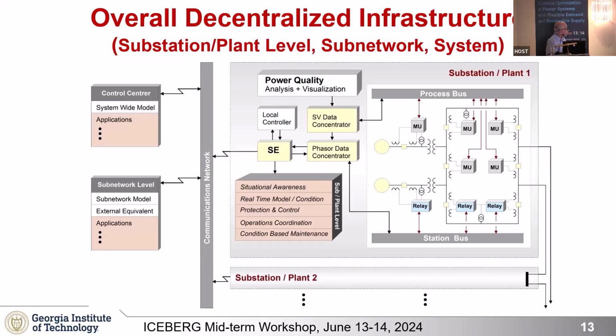The relays, on the other hand, provide phasors. That's another issue, because different manufacturers may use different algorithms for computing the phasors, so we do have errors in the phasors as well. What we can do is take the data from the process bus, convert it into phasors, and populate the station bus as well.